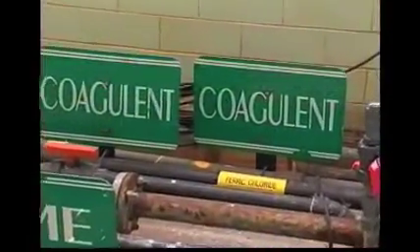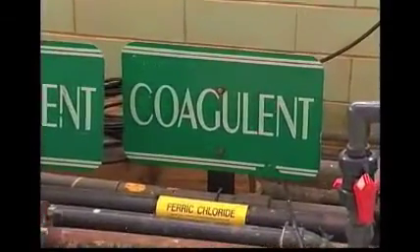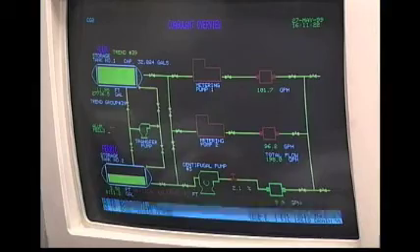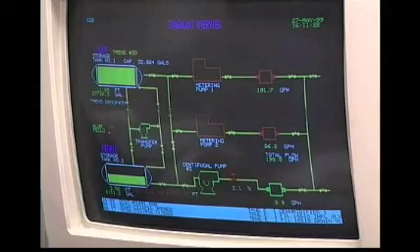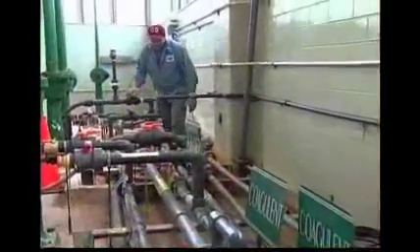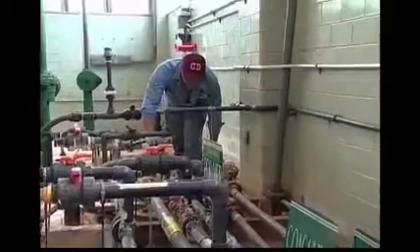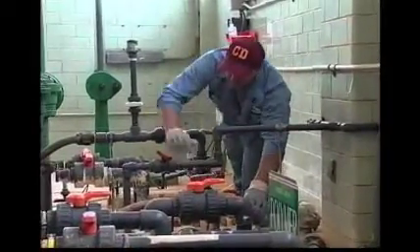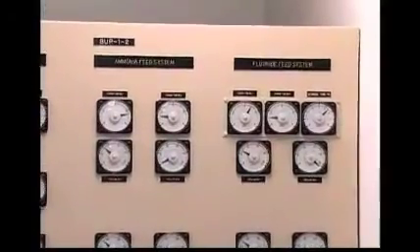Coagulation, controlled here in the process control room, is a step in the process to help settle out small particles in the water. These particles are smaller than the human eye can see and have a slight negative charge on them. That charge causes them to repel one another and keeps them suspended, sort of floating in the water. Chemicals need to be added to help the particles begin to coagulate, or cling to each other.